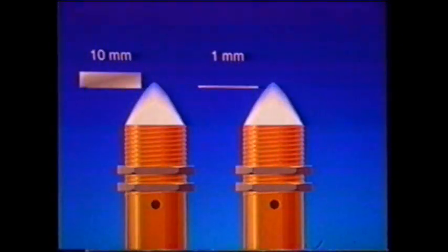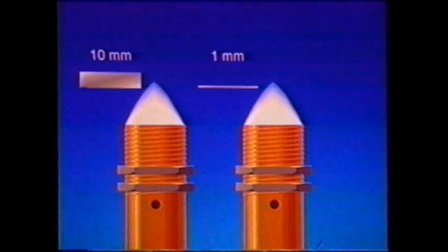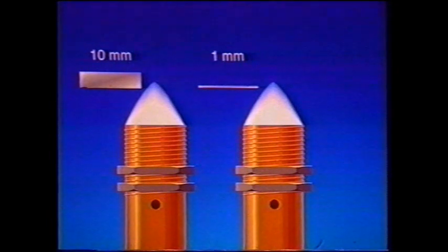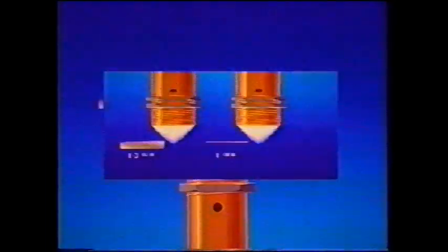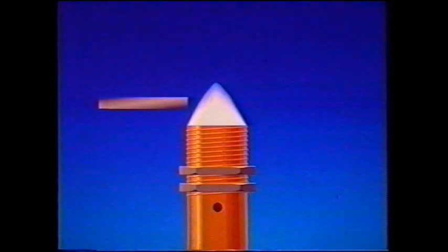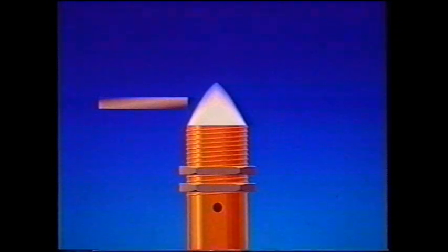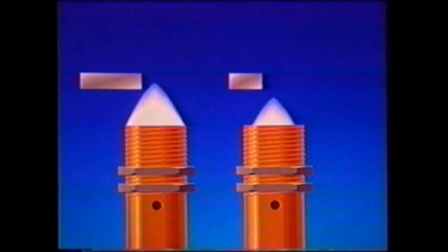Target thickness normally doesn't affect sensing range. For very thin targets, such as metal foil, the actual sensing range may be longer than the nominal range. The size of the target does affect the actual sensing range. The specified range is based on a target that is large enough to cover the entire active face of the switch. If the target is smaller, the turn-on, turn-off graph will be different and the actual range will be shorter.